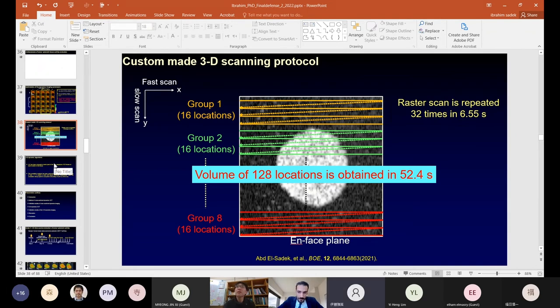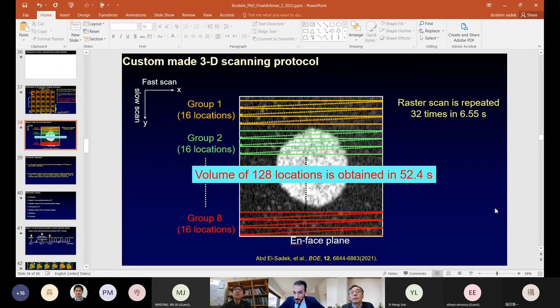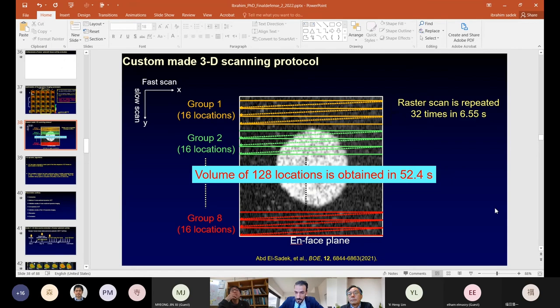Professor Ito asked: what hardware or protocol improvements would allow faster 3D image acquisition? Ibrahim answered that optimizing the scanning protocol through software design could increase scanning speed. The hardware limitation is the 50 kilohertz acquisition speed — one A-line is captured in 0.02 milliseconds, which is the hardware ceiling. As suggested, decreasing the number of A-lines per B-scan could increase acquisition speed. However, the key question is whether a very high-speed OCT system could reduce measurement time — and whether the biological activity being observed (slow metabolic activity) allows for shorter acquisition time windows.